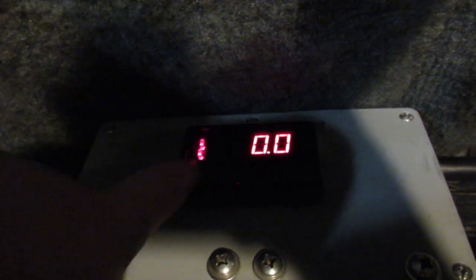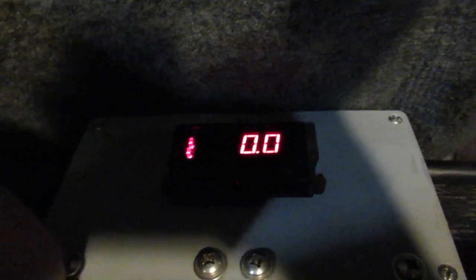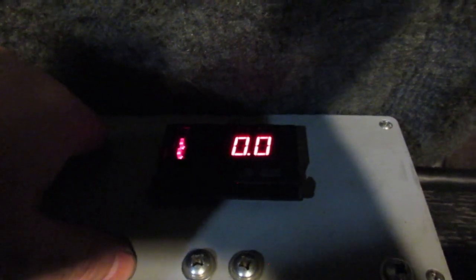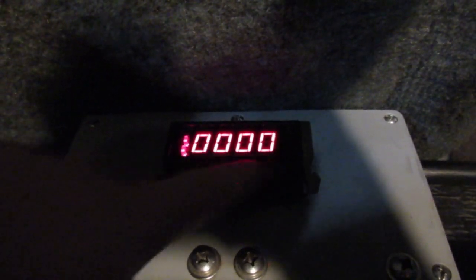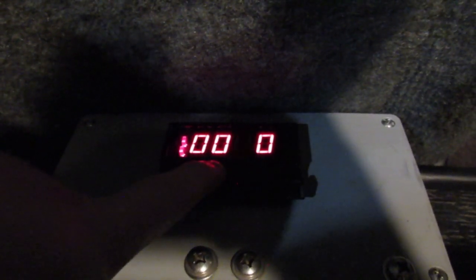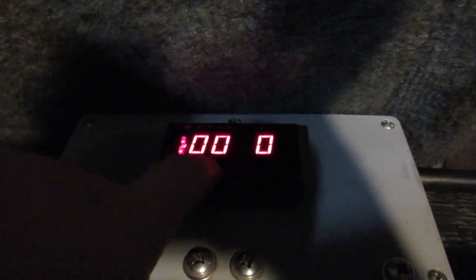If I pick number 4, which was the default on this sensor, we are seeing 0 volts. That's what happened when I first plugged in the meter and plugged in the charger buddy to test it. I was like, oh my gosh, it doesn't work, it's not seeing the pack voltage. What's going on? Well, I just forgot to set this so it was using the 500 volt lead, not the 100 or 10 volt or whatever it was actually looking for a voltage on.